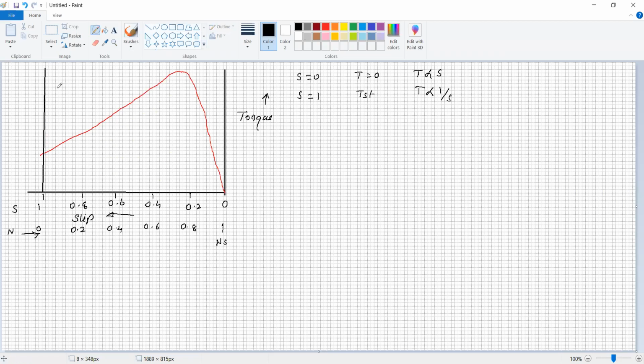So this is the starting torque. It is the starting torque, and this is your maximum torque. So this is T maximum, maximum torque. This maximum torque becomes maximum at slip S, where slip S is equal to R2 upon X2, or when S X2 is equal to R2, the torque becomes maximum.